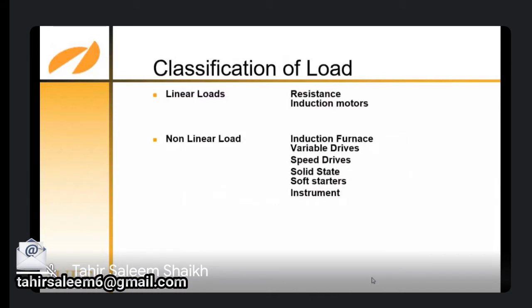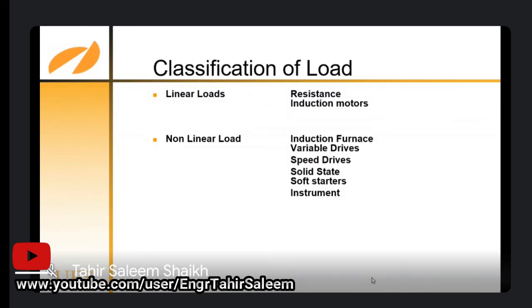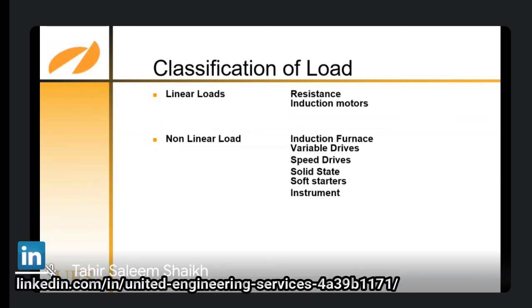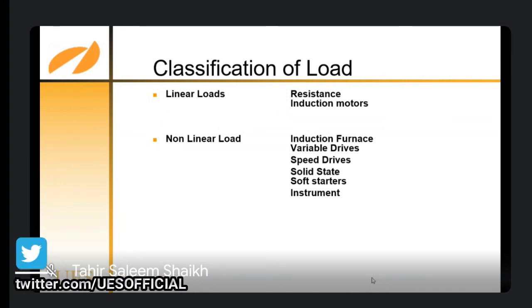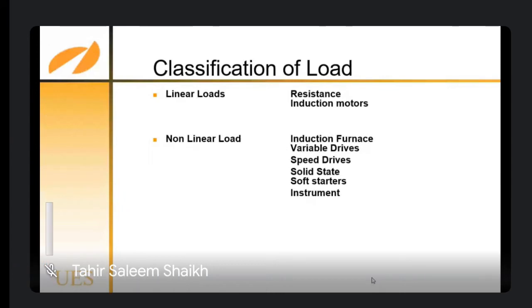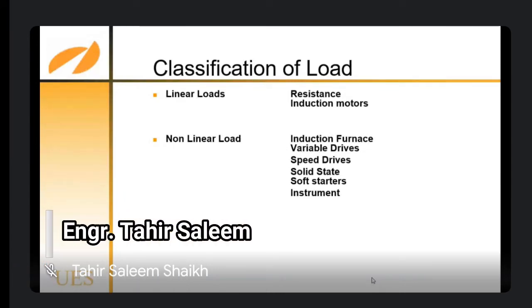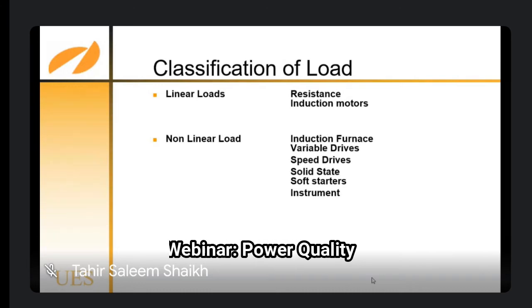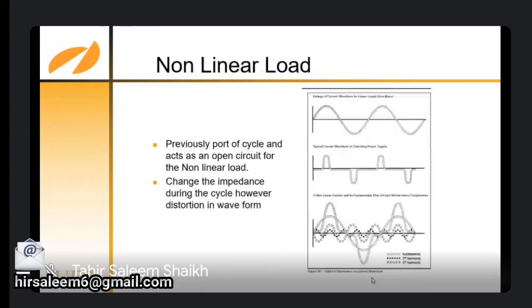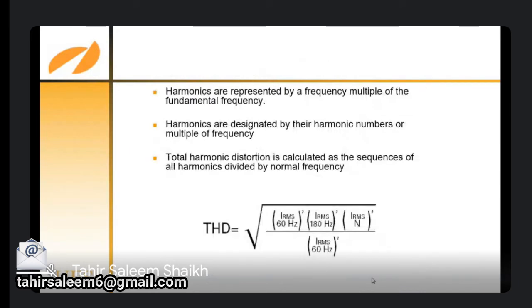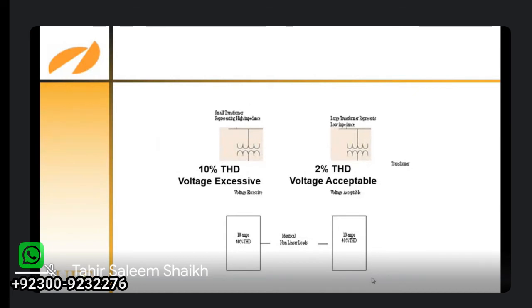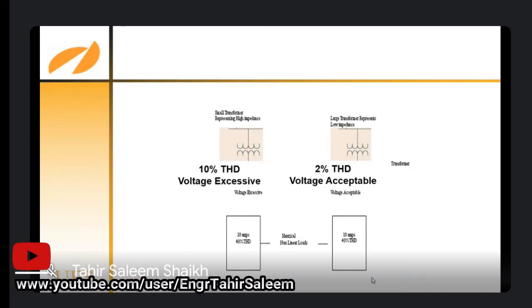Now, if you are designing something and introducing a VFD or UPS or any other non-linear load, such as induction furnaces, variable speed drives, solid state soft starters, instruments, all of these are non-linear loads. So I will give you some solutions which I prefer, so you will see how much they can impact, because these are costly affairs. Either you design for it in the main design, or your maintenance will give you this sort of problem. The first solution, which I discussed earlier and is the easiest for harmonic distortion, is to oversize the components.